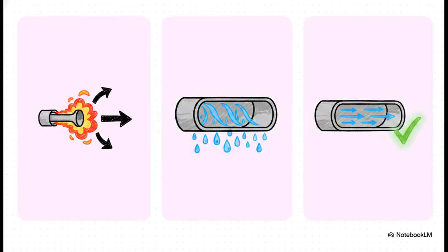When other contractors try to just eyeball the sizing, you run into some pretty major issues. If your ducts are undersized, they literally choke the system, which causes those localized hotspots I just mentioned. But, bigger isn't always better. If your ducts are oversized, the air velocity actually drops. The system doesn't run long enough to properly dehumidify the air, leading to overall inefficiency and major indoor humidity issues. It's like Goldilocks. It has to be the exact right size.